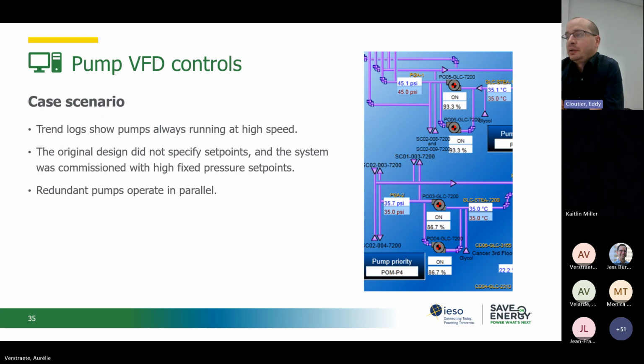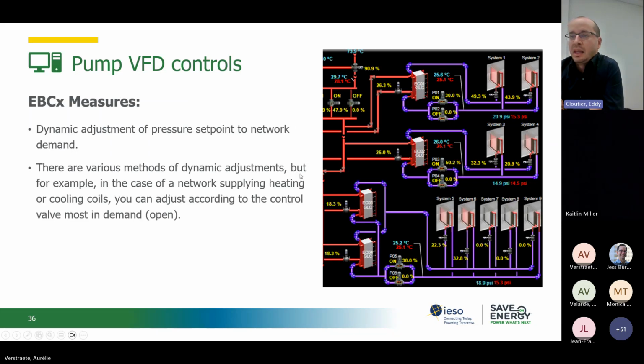So a first example is on the speed control of pumps. A lot of the time, you could have the same example with fans. In that case, the trend logs demonstrated that these pumps were always operating at relatively high speed. And the designer, unfortunately, had not specified any pressure set point during the design. So the contractor did the best they could, and they adjusted the operation with a relatively high pressure set point. This forced relatively high speed operation at all times, and even the need to operate, as you can see on the graphs, 2 pumps in parallel, while they should not operate in parallel at all.